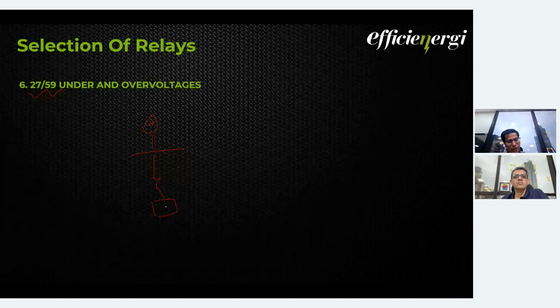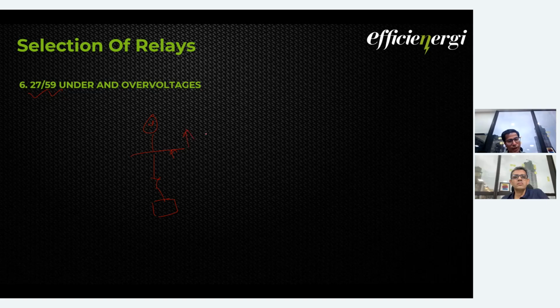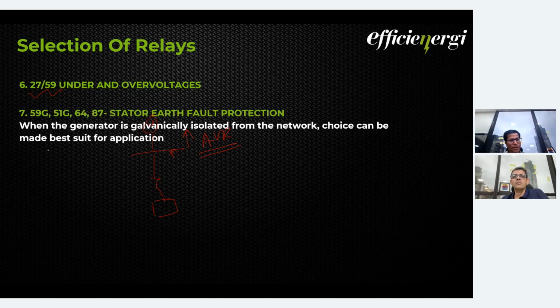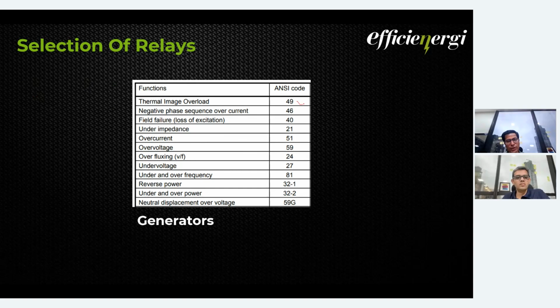Then we have 27 and 59, under voltage and over voltage, which you must be aware of, because on the generators, mainly if there is a load shedding of a severe magnitude, the voltage on this bus may rise very heavily before your AVR comes into the picture. So for that, over voltage and under voltage protections are required. For the stator earth fault protections, I need some extra time to explain how this works. We also have stator earth fault damage curves that we'll be explaining in the next session. So these are basically the ANSI code functions that we are using.